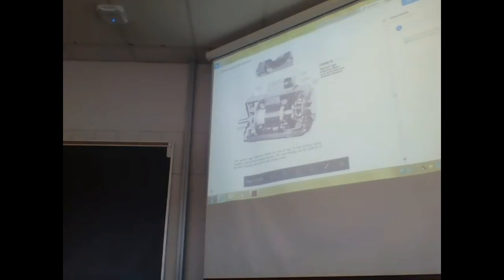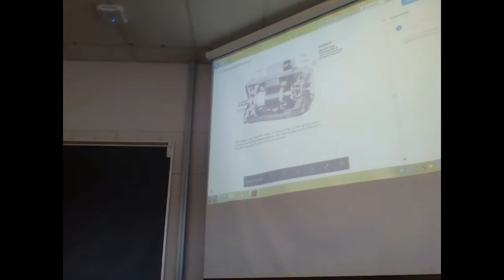This motor shown here is a single-phase motor. It has a squirrel cage rotor and stator, but it also shows a starting capacitor, which is necessary because in a single-phase motor you don't have that rotating magnetic field with the three phases. Also, a single-phase motor has separate starting windings and run windings.